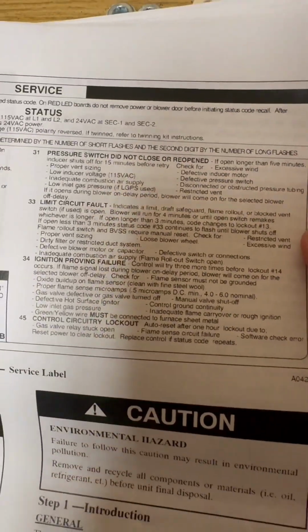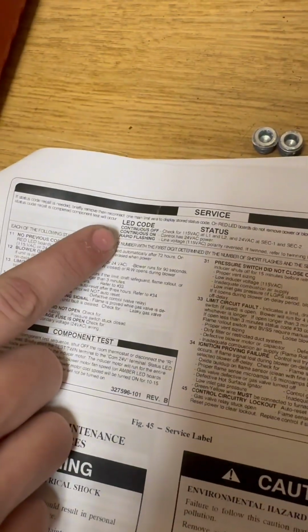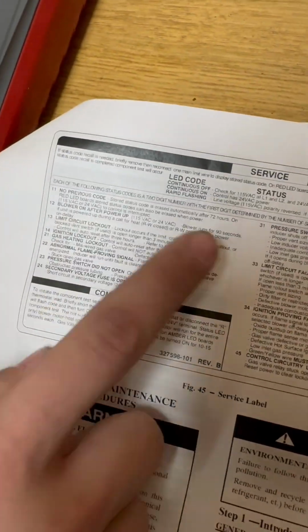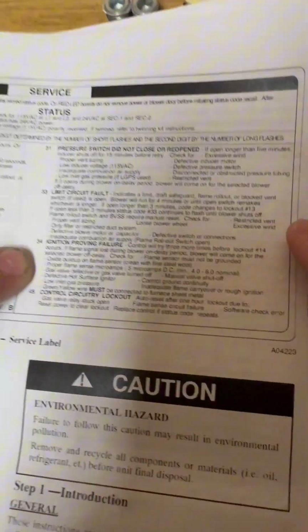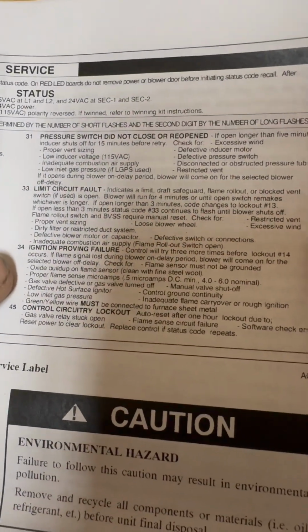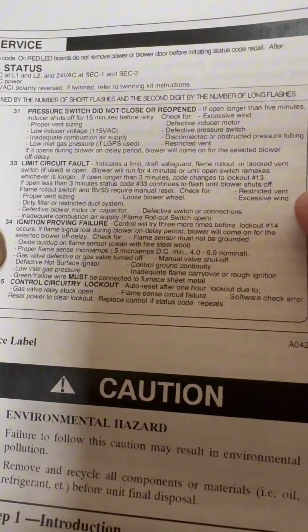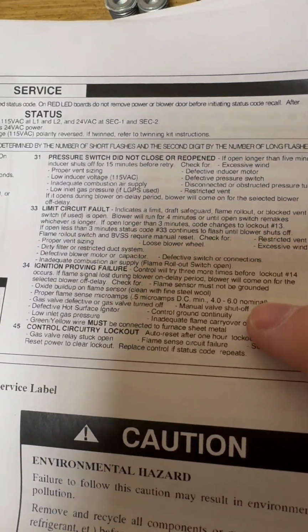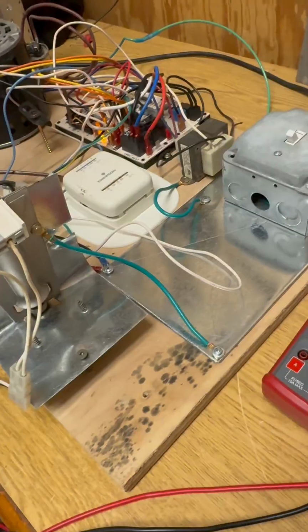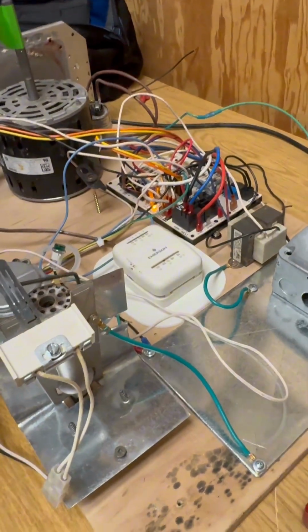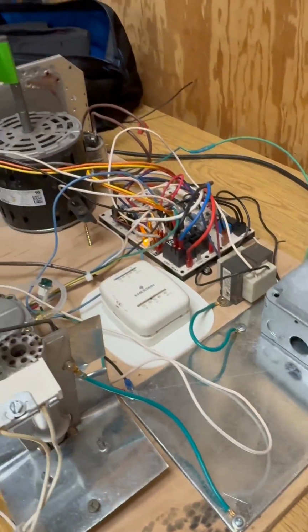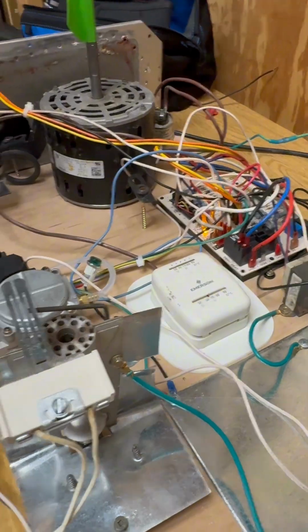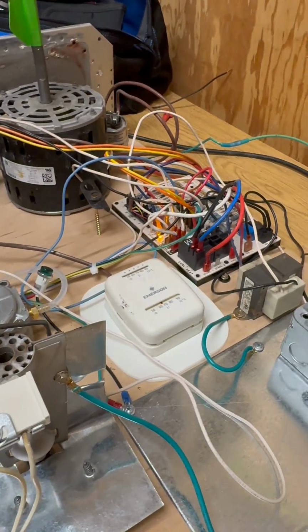So we are now on our code page. So up here it says LED codes. This gives us a list of all our codes, and we are getting code 34, ignition proving failure. So all these are possibilities underneath of the code. So now we have to diagnose based on what the code tells us. So we know we're not getting any voltage to our gas valve, so we're going to check if we got voltage at our board.